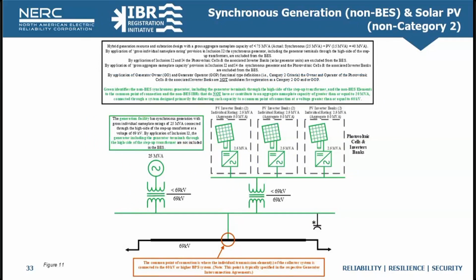This is another example that depicts a hybrid generation resource and substation design consisting of synchronous generation and solar with an aggregate nameplate capacity of less than 75. This hybrid generation resource consists of one synchronous generator rated at 25 MVA and 6 inverters individually rated at 2.5 MVA, making up the solar component for an aggregate nameplate capacity of 40 MVA. The common point of connection here, again identified by the orange circle, is at a voltage of 69 kV.